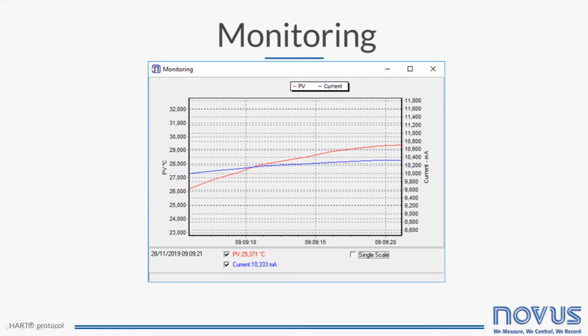Okay, so we have 63% in two answers, field diagnostics without removing the field device from the plant, and the other, digitally monitor without need for active current loop. And here 50% to other two questions. Easy to upgrade 4 to 20 milliamps legacy systems for digital communication and can be used or replaced on HART system of any brand. So we really appreciate your answers. Thank you again.